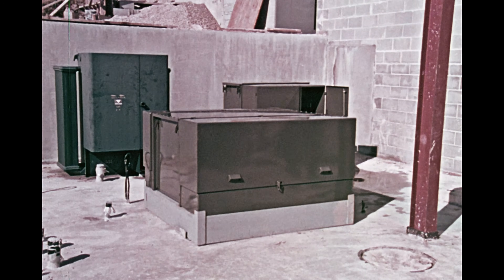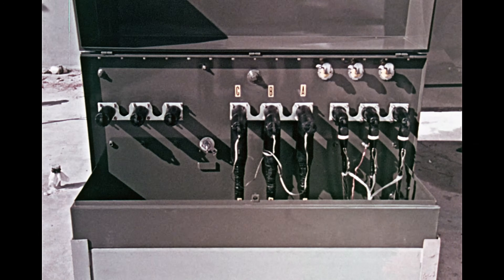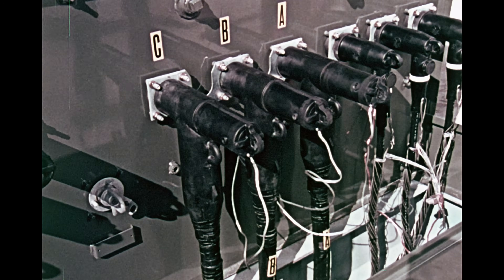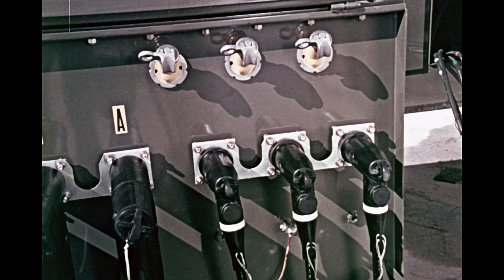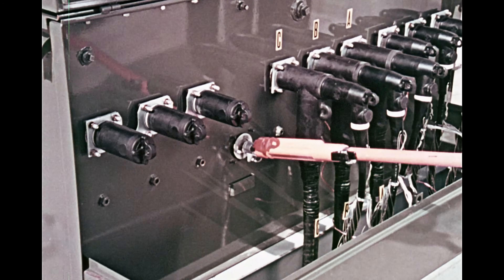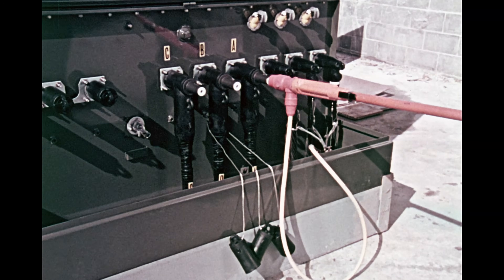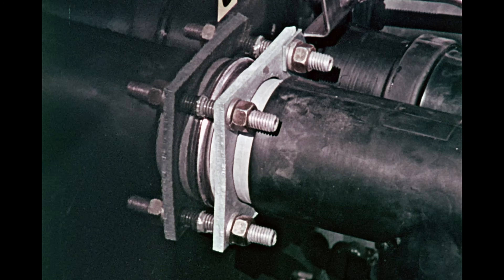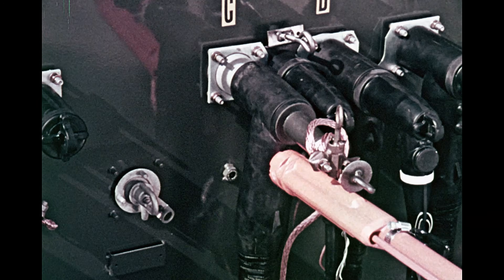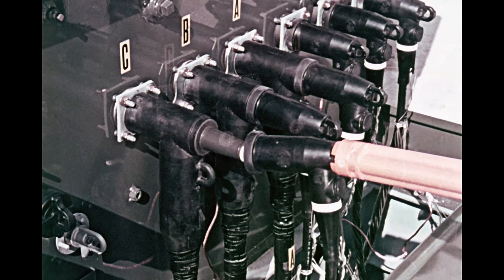Here is another breakthrough: a 600 amp sectionalizing center in a packaged unit. Designed with such simplicity, it provides a space-saving ratio of more than 5 to 1 over conventional systems, and surprising dollar savings too. This compact box has a 600 amp three-phase feeder, looped through with five 200 amp three-phase fused taps. There's real safety from a well-grounded visible break, operated by standard 15 kV accessories. Break the 600 amp circuit, test the circuit, plug in the grounding elbow, insert the visible break tool — and the circuit can be opened with the ease and safety of hot stick operations. The back of the connector provides a fully rated 15 kV, 200 amp load break tap to be used while the equipment is being maintained.